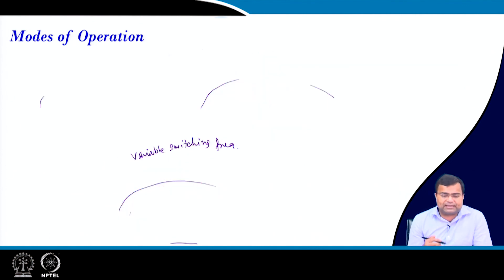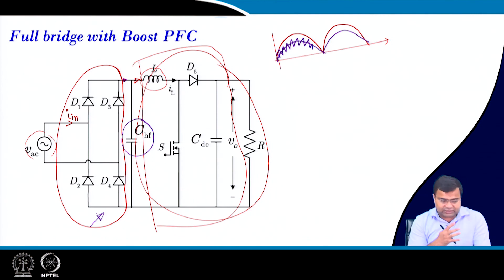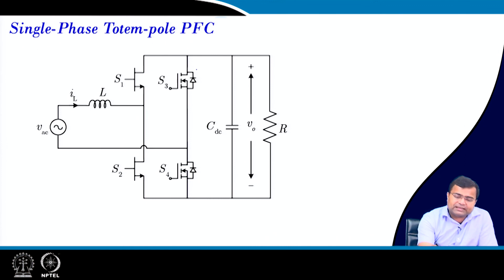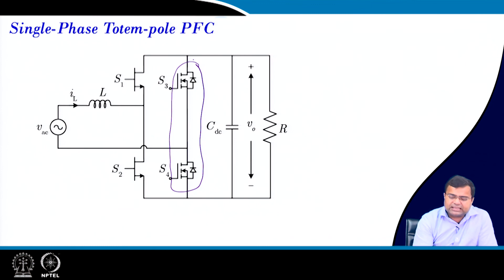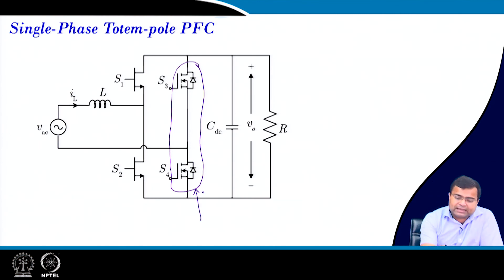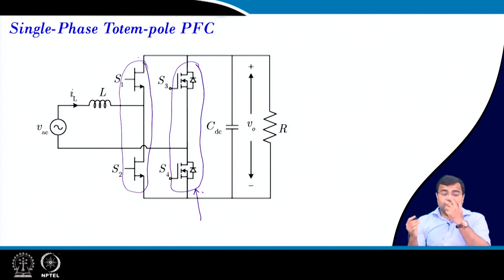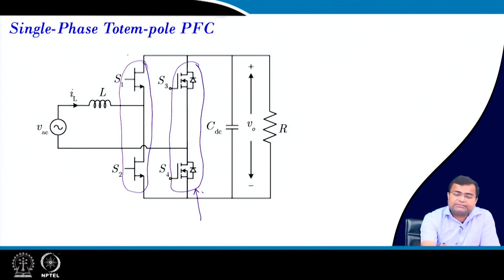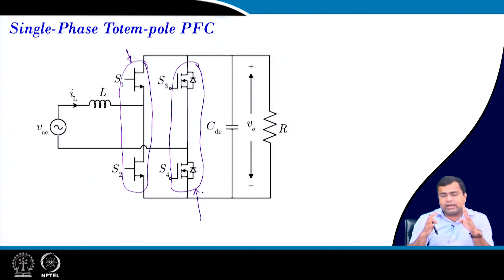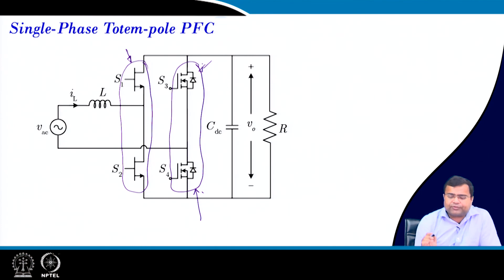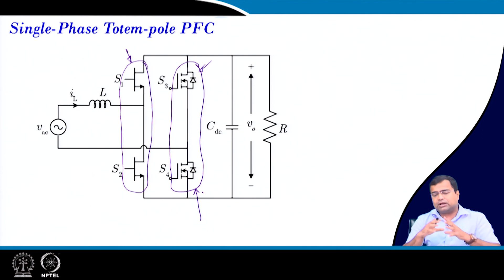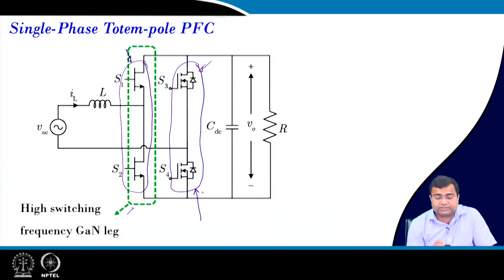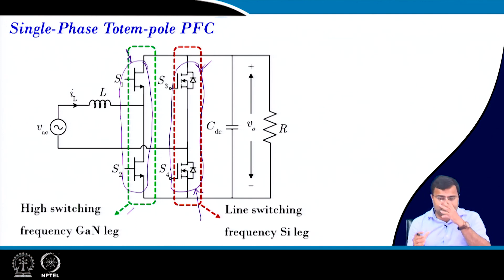For totem pole PFC, the conventional diode bridge is replaced. With wide bandgap devices, one half-bridge of diodes is replaced with MOSFETs whose body diodes act as the diode network. One leg operates at line frequency (50 or 60 Hz), while the other leg uses high-frequency wide bandgap devices — specifically GaN devices or silicon carbide. In this course a GaN-based totem pole PFC will be demonstrated, where the GaN leg operates at hundreds of kilohertz and the silicon leg operates at low line frequency.